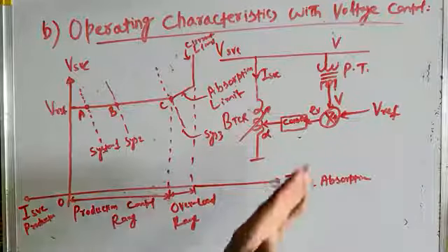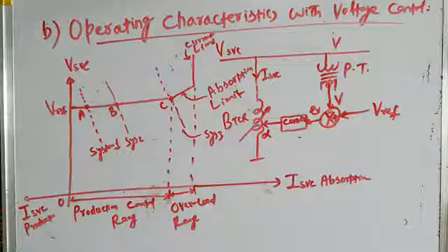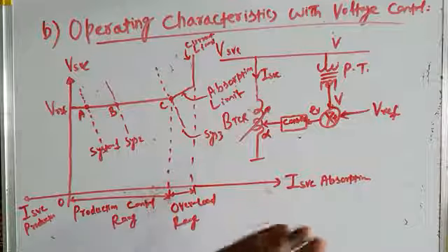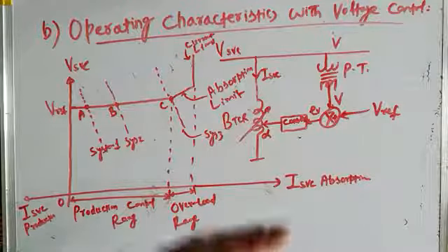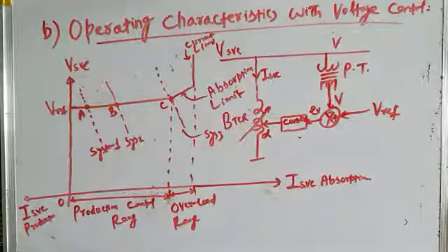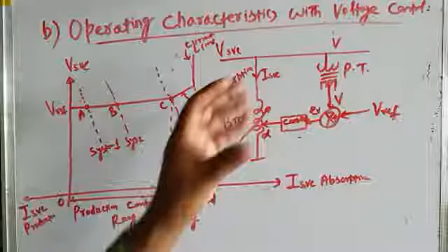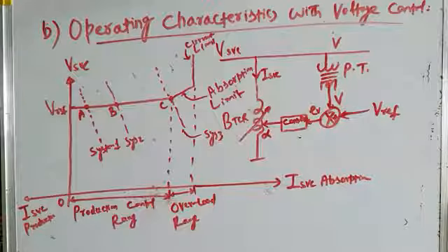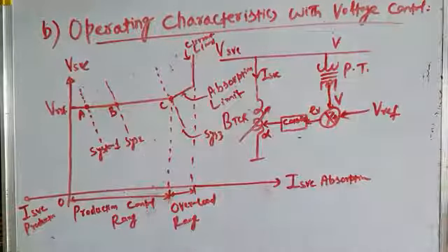On the other hand, if the load is operating at a leading power factor, it is drawing leading power factor current, or leading VARs. In other words, it is generating reactive power and injecting that reactive power onto the transmission system, and there will be excess reactive power on the transmission system, and that will result in negative voltage drop across the transmission line reactance, and the voltage of the bus will increase.